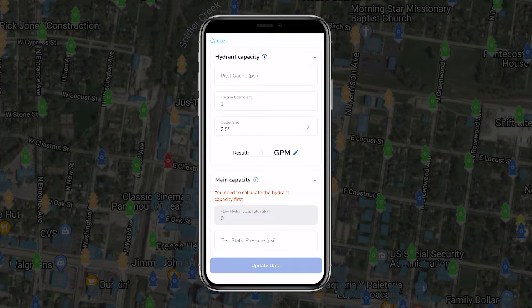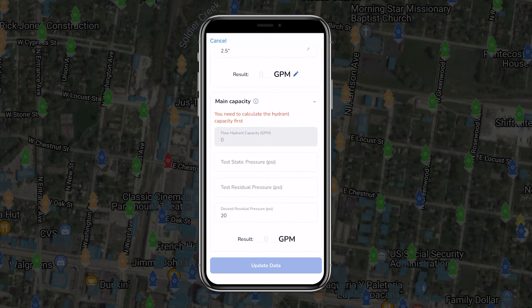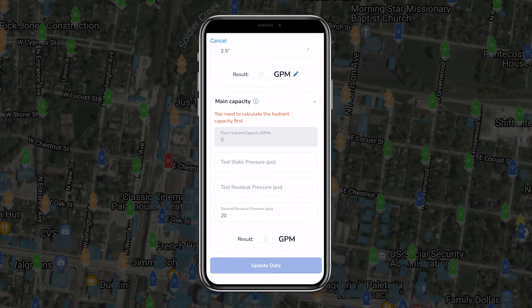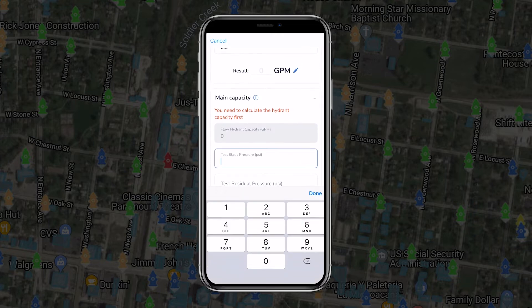To begin, one team member will attach the cap gauge to the test hydrant for measuring static and residual pressure. They'll open the hydrant valve and then use the cap gauge valve to vent air or other contaminants that could be affecting readings. They'll then close the cap gauge valve and take the static pressure reading.